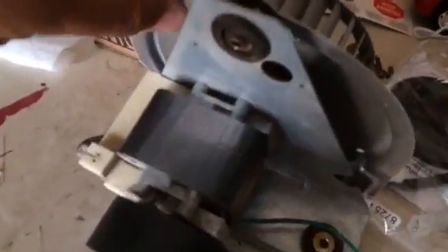Anyway, as I was saying, really all I need to salvage from this whole assembly is the mounting, the cover, and the vibration isolator here. I get a new blower with the kit. This blower's got to come off. I get a new, I believe this is a flywheel, with the kit. So this flywheel comes off. The motor gets chucked. All I need is the cover and the vibration isolator.